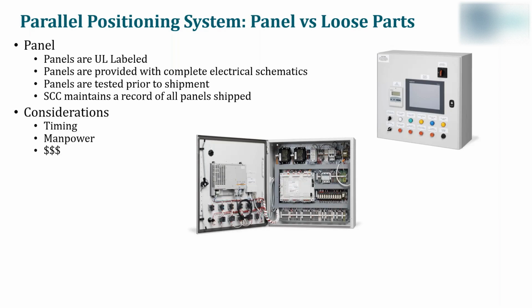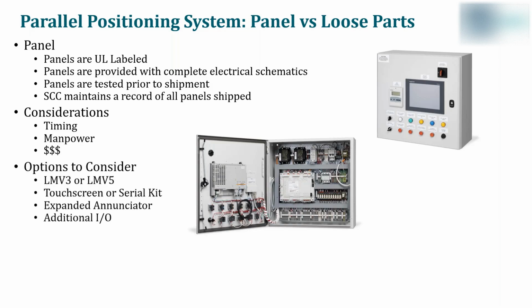Next, considerations. Considerations include, what is the timing of the project? Is this something that needs to be completed in the next week or two, or during the next shutdown, which may be 2 months away? Do you have enough manpower? On the average, a panel can cut down installation time by 50% or more, depending on the complexity of the system. And finally, on the average, a panel will be approximately 20% more versus loose parts. However, if you take manpower, drawings, installation time, and material costs into account, the overall cost is substantially less than purchasing the loose parts.